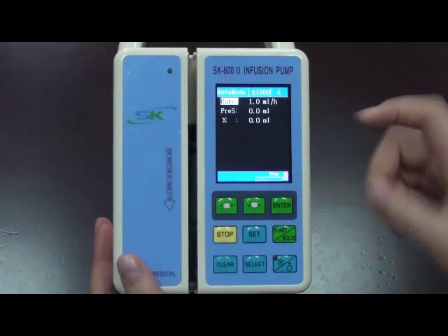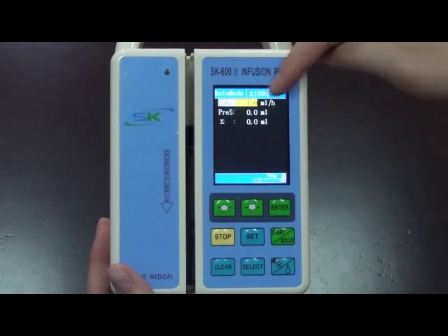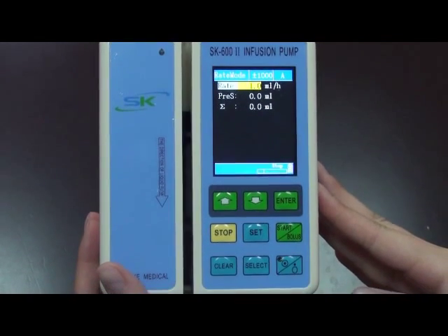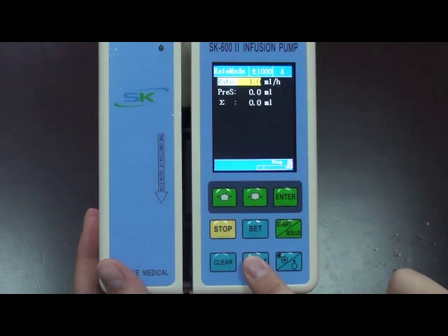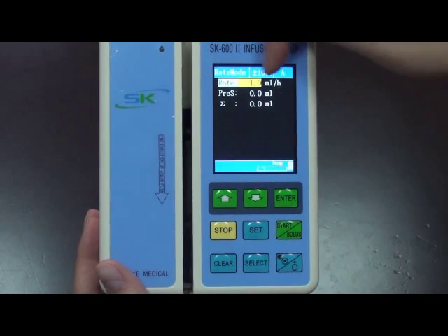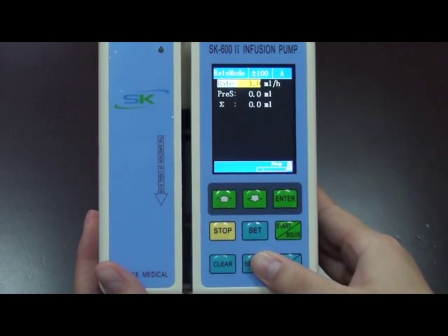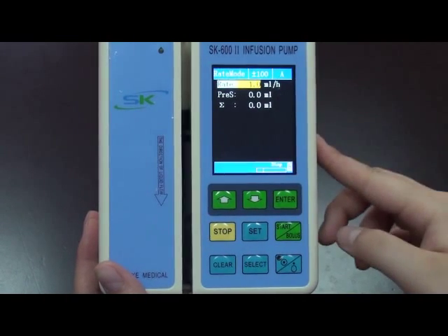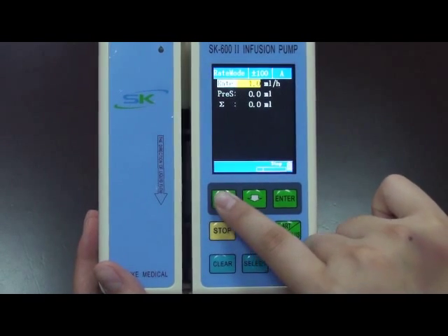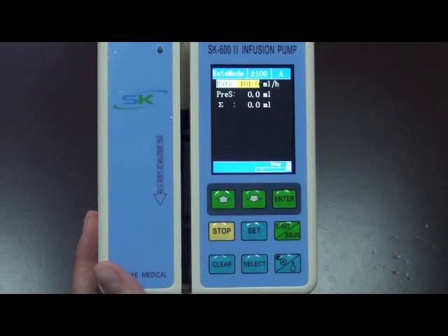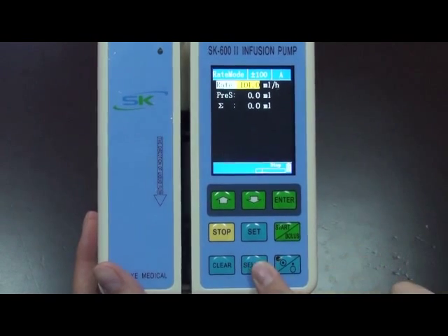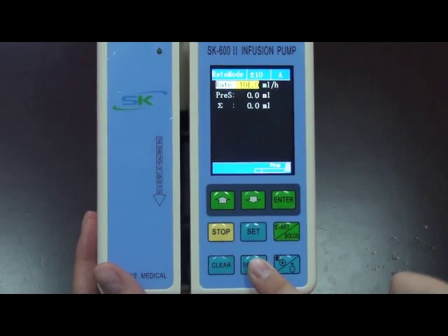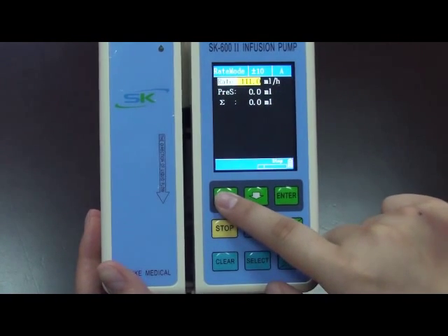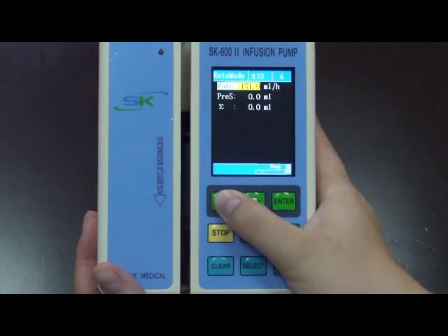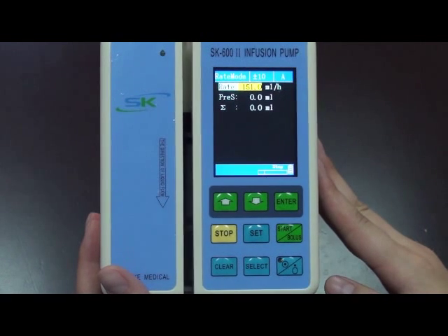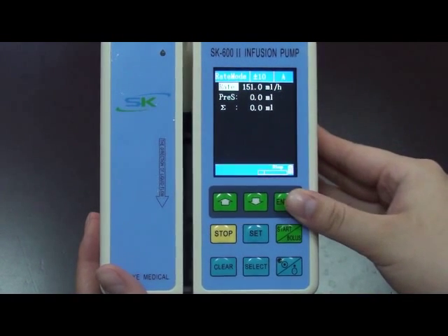Firstly, you press Enter key. Now you can see the rate, this parameter is chosen, right? Then you press Select key. When you press it, please notice this middle value here. Press it once, you will notice it becomes up and down 100, right? Then you press Up key once. You will see the rate is increased by 100. Then press Select key again. Press Up key 5 times. 1, 2, 3, 4, 5. Now the rate becomes 151.